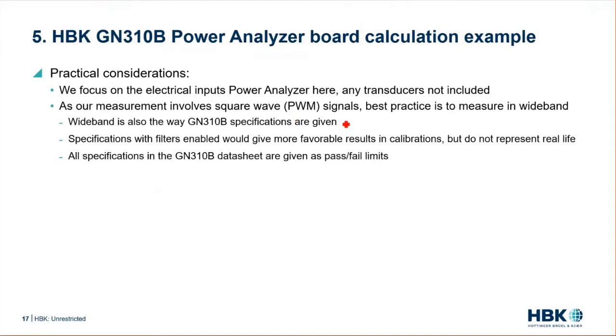This is also the way in which the GN310B specifications are given. One thing you might consider is that specifications with filter enabled — as calibrations are done on sine waves — would give more favorable results, but since they do not represent real life, we have chosen to do all of this in wideband. Also, all the specifications in the GN310B data sheet are given as worst-case limits.